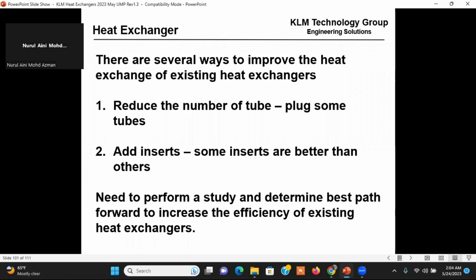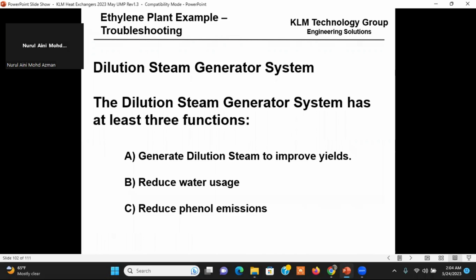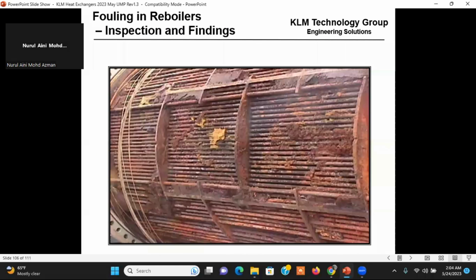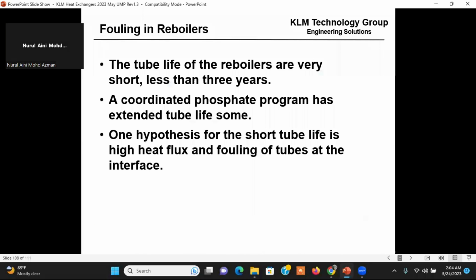You probably need to perform a study, determine the best path forward to increase the efficiency of the existing heat exchanger. So now if you're running a laminar flow, you reduce the number of tubes, you can add some inserts. So these are things that you can do. And then I've got a troubleshooting section, which I'm just going to flip through.